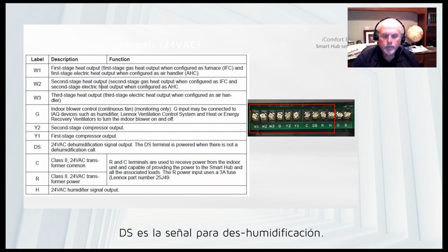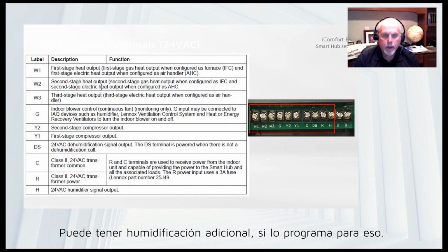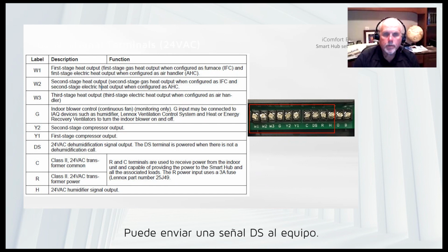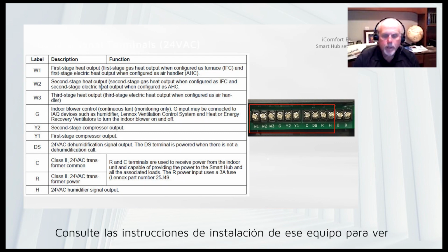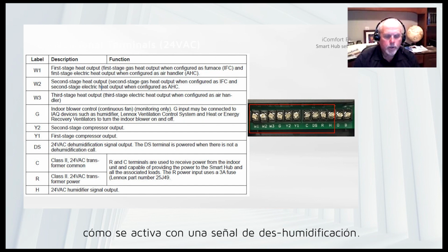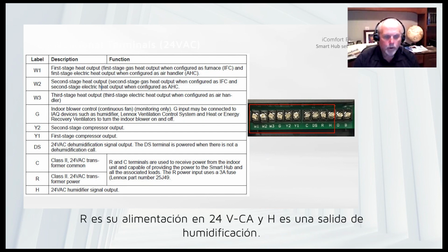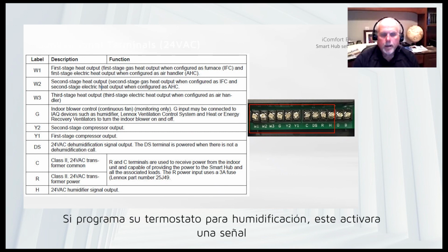DS is a dehumidification signal, and you can have extra dehumidification if you program it for that, and you can get a DS signal out to the equipment. Of course, on some equipment you would have to clip a jumper. So you just have to read the installation instructions for that equipment to see how it operates with a dehumidification signal. C is your 24-volt common. R is your 24-volt power, AC. And H is a humidification output. So if you program your stat for humidification, when it needs humidification, a 24-volt signal will be put out on the H terminal.